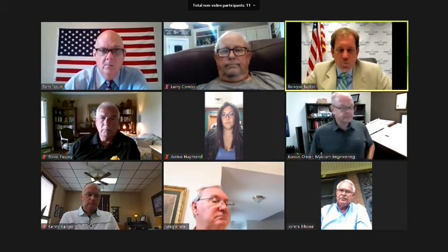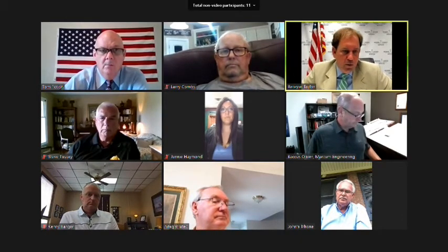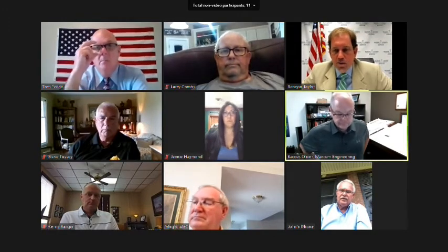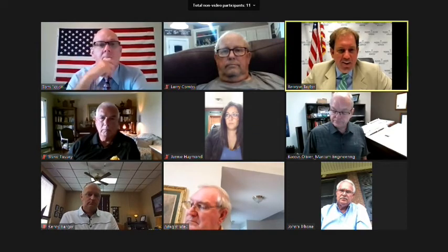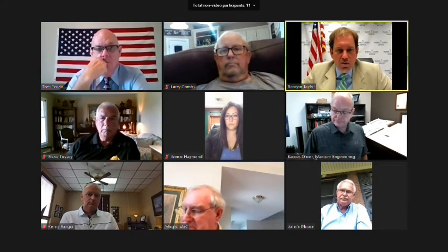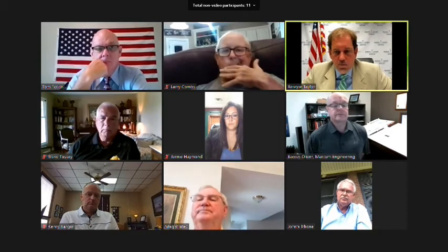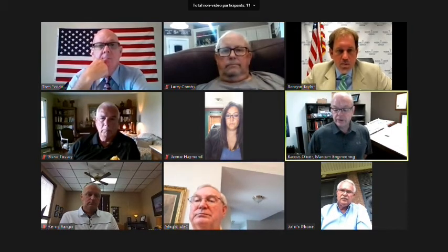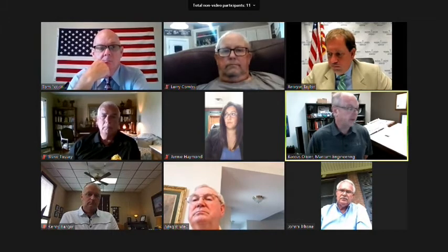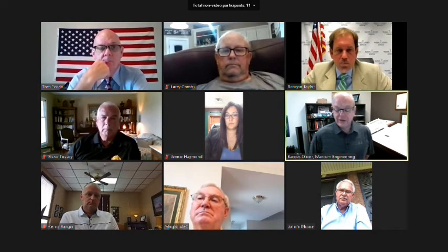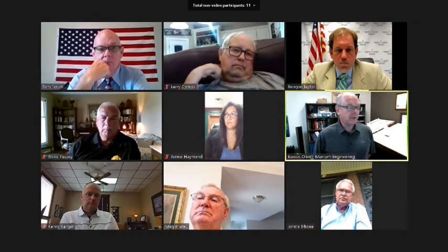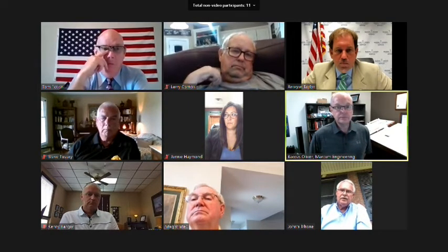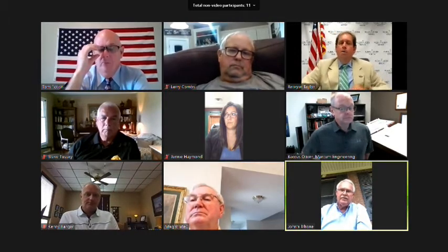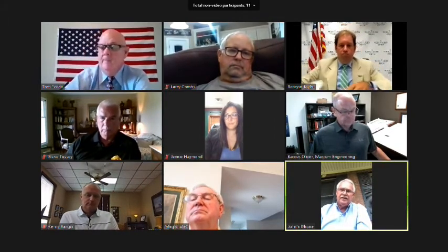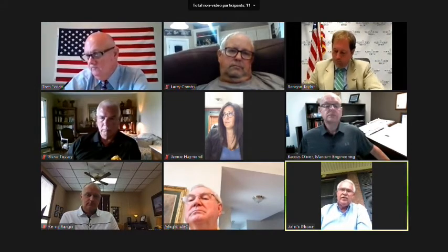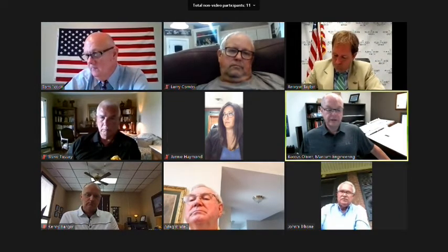Yeah, if you think about that, the majority of the people in the building are here 8 to 5. Mm-hmm. And so from 5 to 8, you could have these electronic controls set so the units aren't running. Right. For an office, only 38% of the day it's occupied. So you have all that other time that you need to be setting back and saving energy. So the $11,000 is on the savings from changing the boiler out to gas. That's not adding the other savings with the other improvements we'll have there. That's correct.